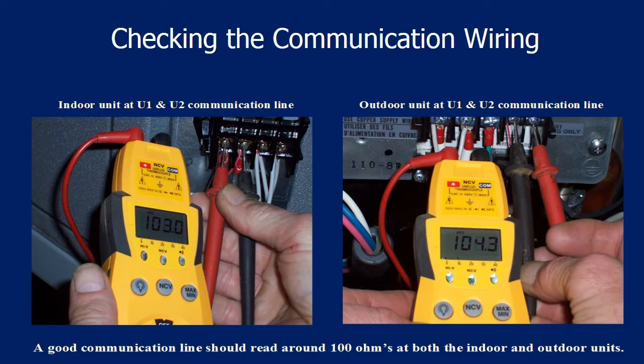The 18-2 stranded shielded control wire should ohm out at around 100 ohms when checked at either the indoor or outdoor unit. If a system fails to address after several attempts, this wire should be checked and verified as good. This wire should also never be run within the same conduit as the power supply wiring. The communication signal is a pulsating DC voltage which is less than 5 volts DC and can usually not be read with an electrical tester due to the rapid pulse rate being generated.